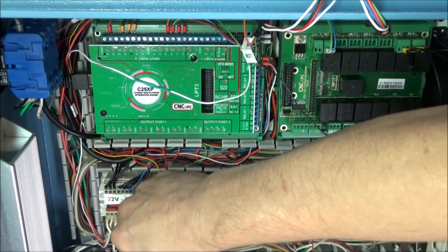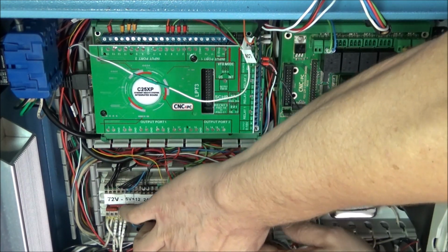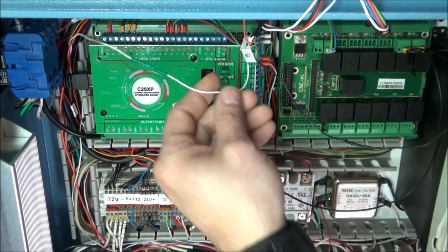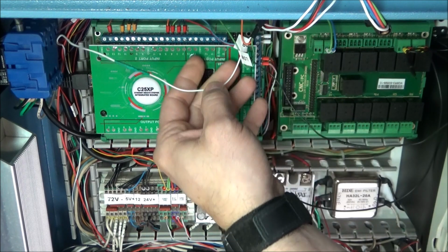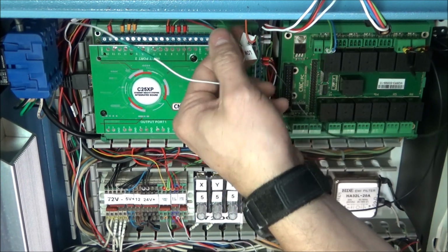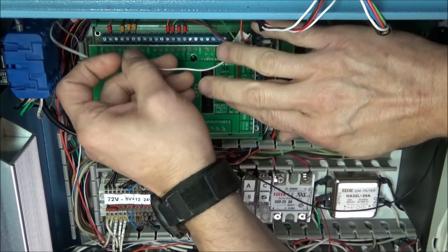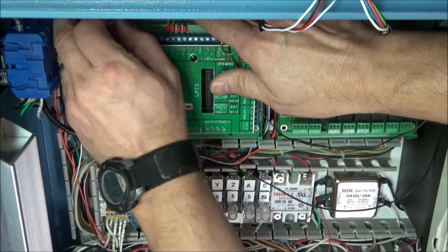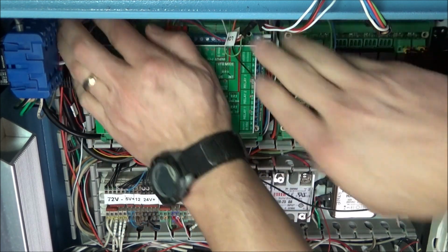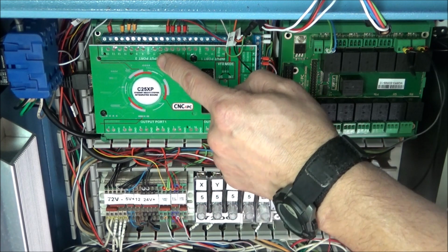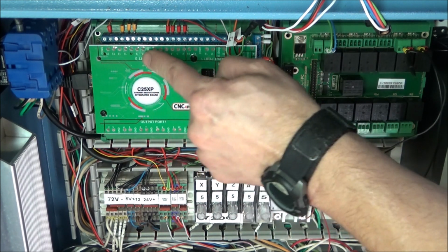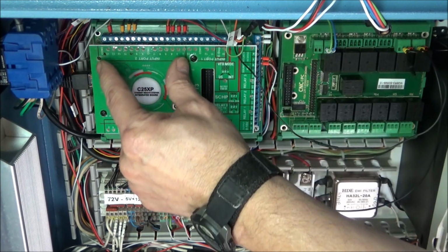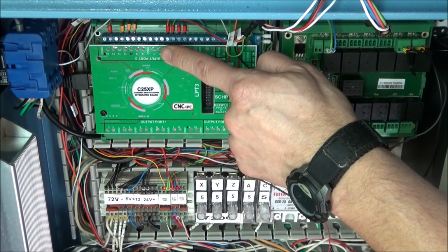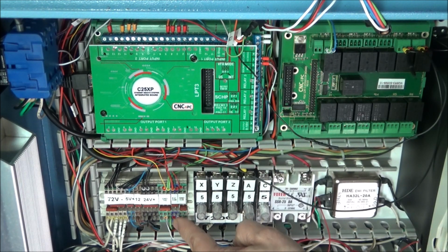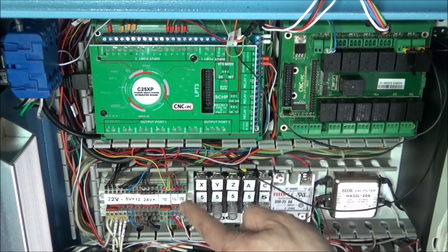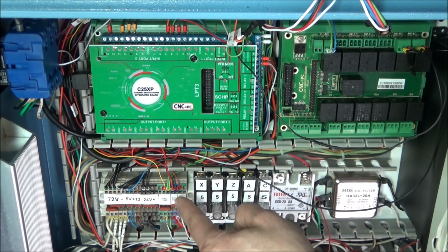We can try to get all this stuff tucked away, but there's one more wire that we need to connect. We've sent 5 volts out to our foot switch and our low air pressure switch, but we need to have a common, and we need to land that on our port 2. So on port 2 here, we have 2 spots for our common, and since the voltage coming into our inputs is 5 volts, we need to land the common from our ground for our 5 volts.